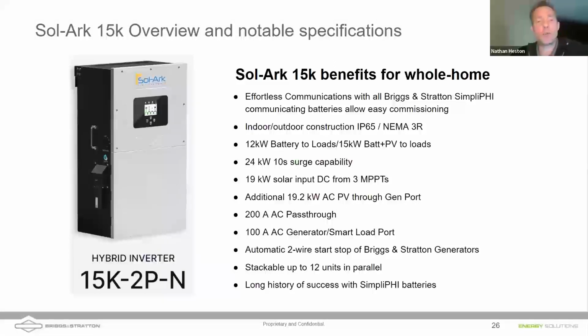You've got 24 kilowatts, 10 second surge capacity. So if you need to start up some big loads, you can get up to 24 kilowatts for 10 seconds. You've got 19 kilowatts of DC input on solar, 3 different MPPTs, right? Which means that you can have different facing arrays, one facing east, one facing south, one facing west if you want. You can also do an additional 19.2 kilowatts through the Gen port or the Smart Loads port, which was what we were talking about earlier. And this big feature of 200 amp AC pass-through, so I can bring in 200 amps from the grid.